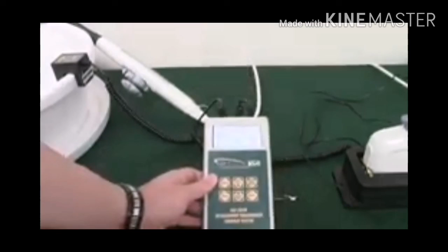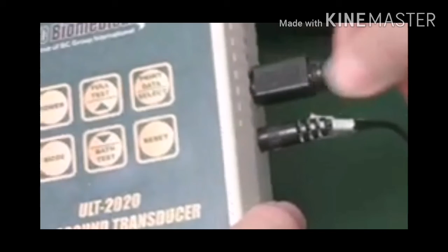Once on, simply press Full Test to begin the test. The machine will do all the work. You just need to wait for the results. When finished, Pass or Fail will appear on the screen, indicating your results. If a printer is attached, the results will print off in detail along with a pass or fail. Repeat this process for all ultrasound transducers.